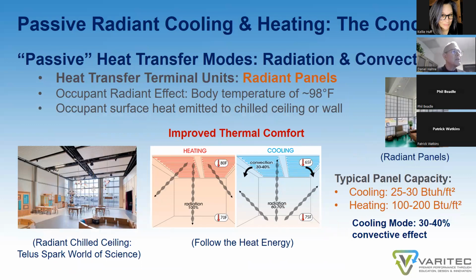In a passive heat transfer mode for exploiting radiation and convection, one of the solutions is the use of radiant panels. These are metal surfaces that reside in the ceiling. In fact, they can actually compose a ceiling in their actual design. And by cooling a ceiling, you actually absorb warm temperatures or energy emitted from warm surfaces within that space into that cooled surface. So consequently, radiant systems are conducive to better thermal comfort because an occupant's emitted thermal energy is actually absorbed within the surface of the chilled ceiling. The other option is to heat the ceiling in wintertime at an adequate temperature so you can emit the radiant energy to heat surfaces within that space.